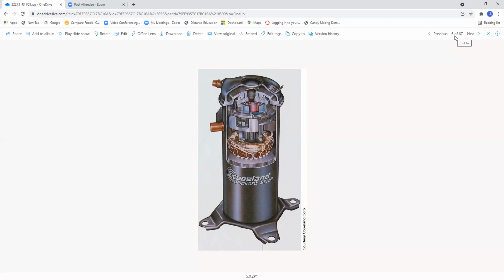Please remember, when you are changing a compressor on a heat pump, I don't care what brand it is, you need to make sure that the compressor you're installing is rated for heat pump duty. There's a big difference between a heat pump compressor and a standard air conditioning compressor.